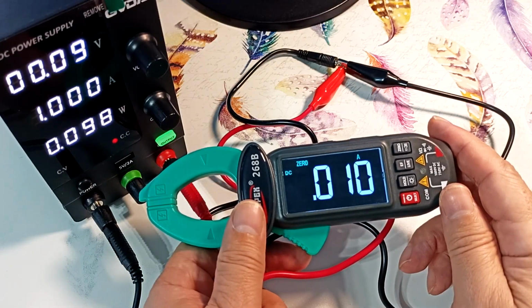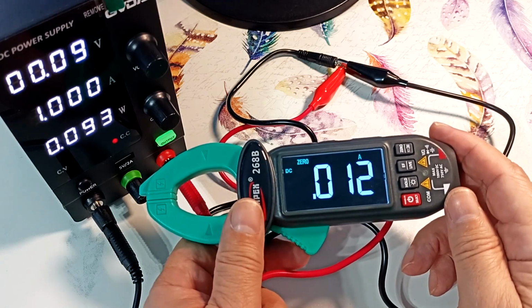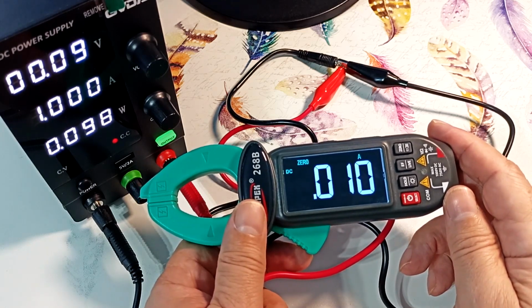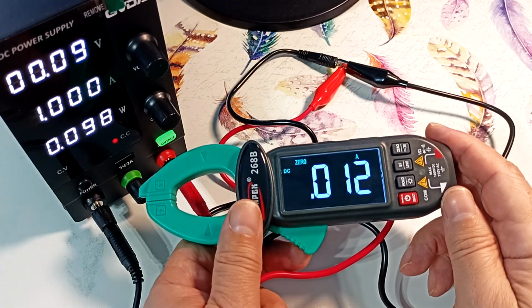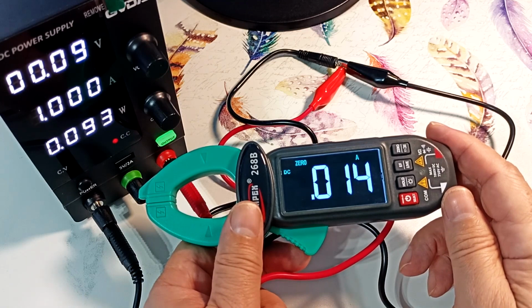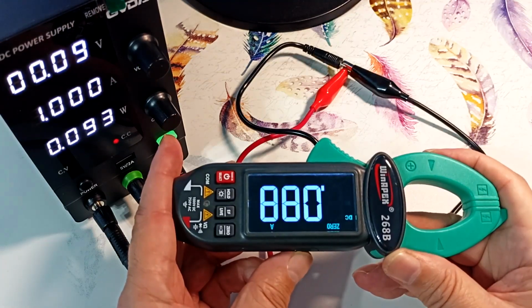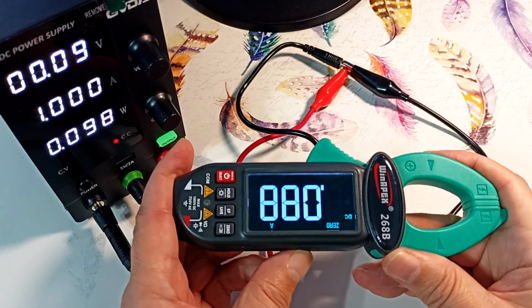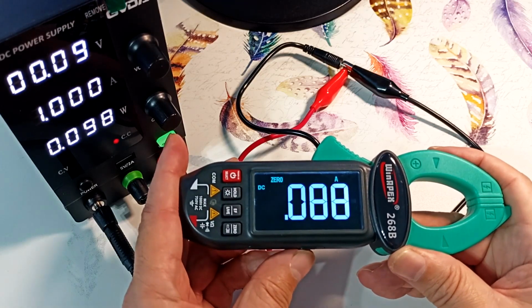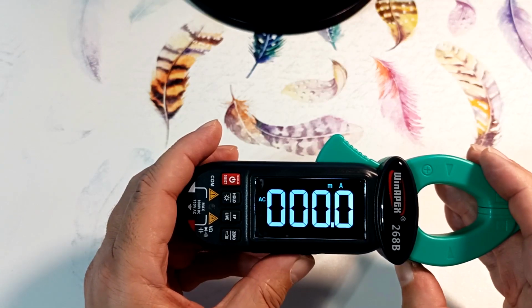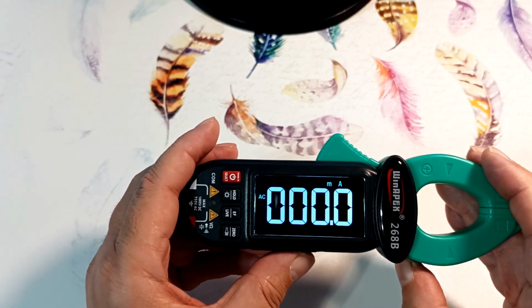I don't like that even without measuring the current, the device readings range from 20 to 40 milliamp. Therefore, they cannot accurately measure small leakage currents when measuring direct current. To turn the indicator over, hold this key for a long time. Now our indicator has turned upside down. Use the side key to switch the device to the alternating current measurement mode.